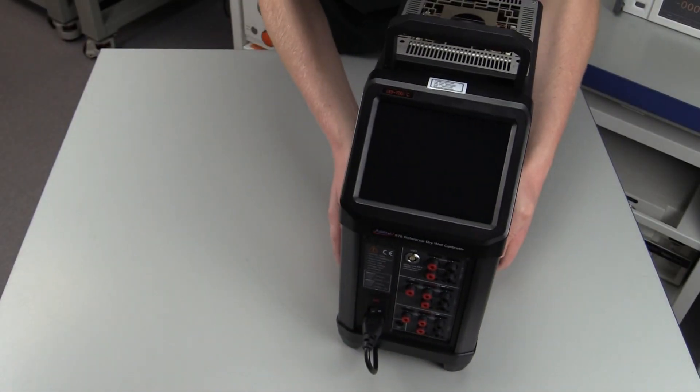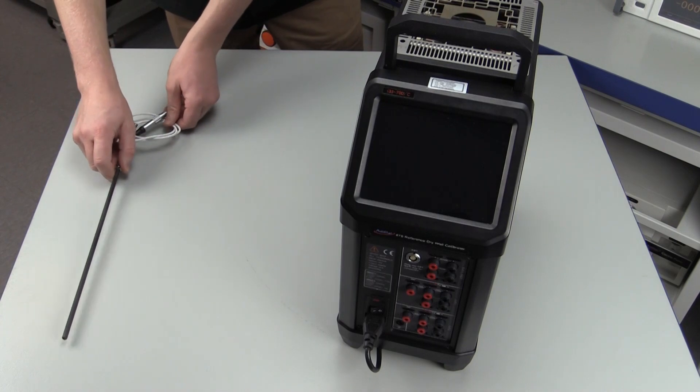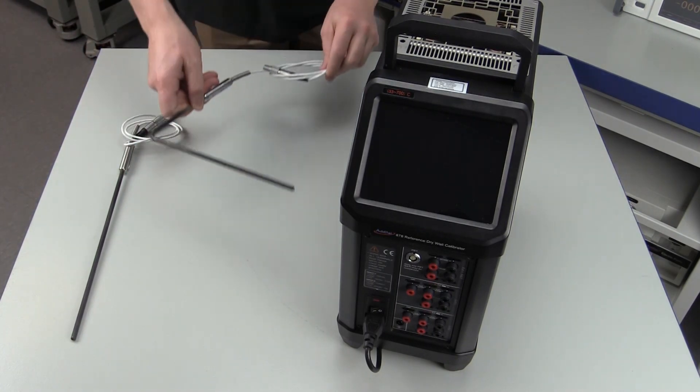To begin, all you will need is the Additel 878-700 reference drywell calibrator and your reference PRT or PRTs that you would like to anneal. In this case, we will anneal two probes simultaneously.